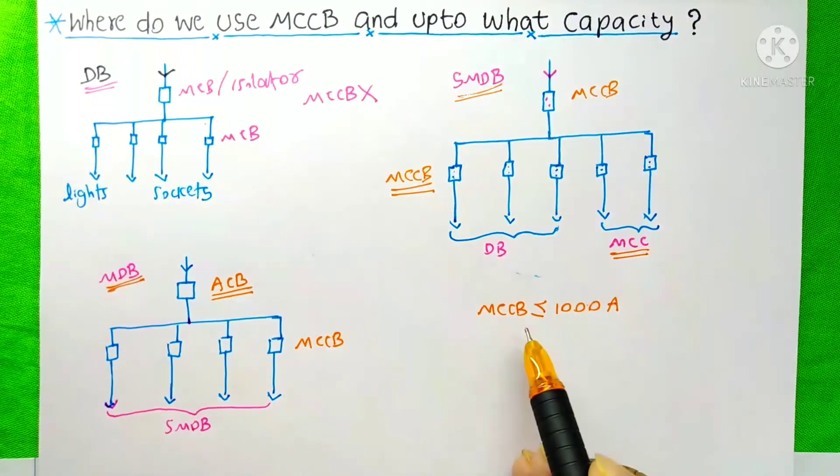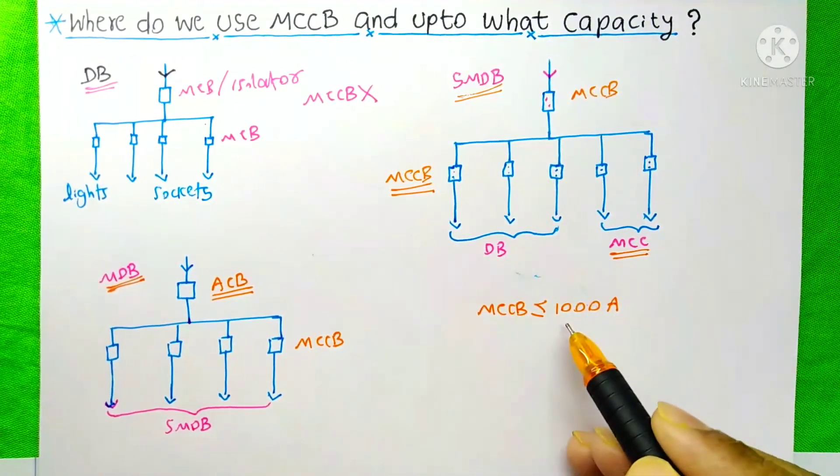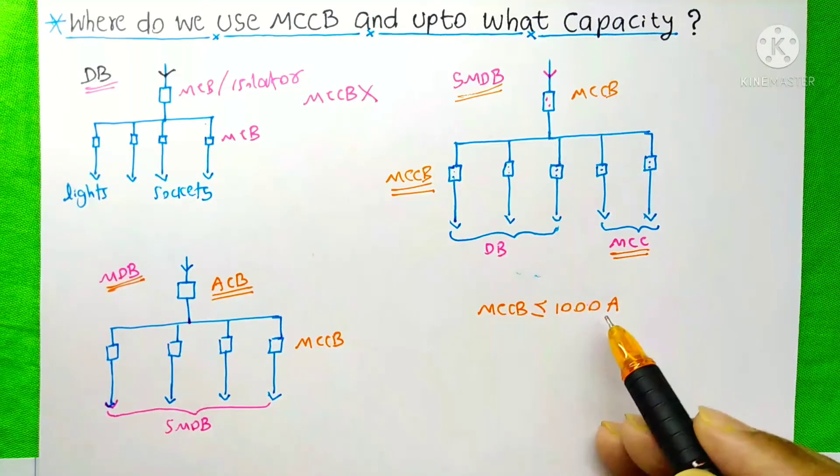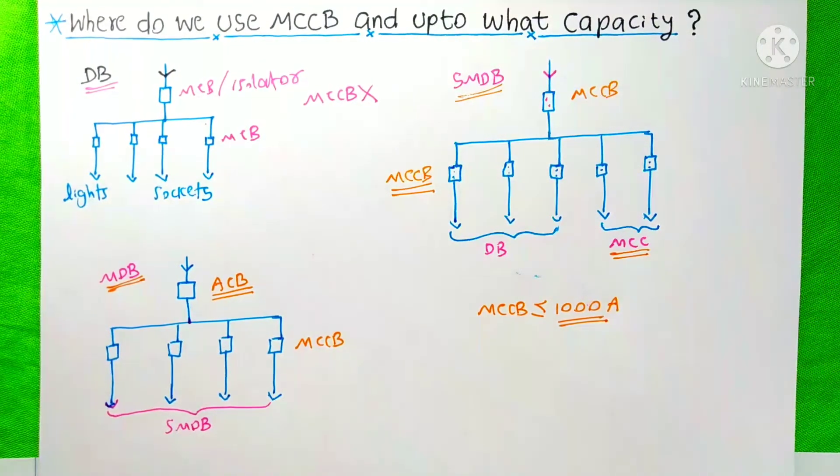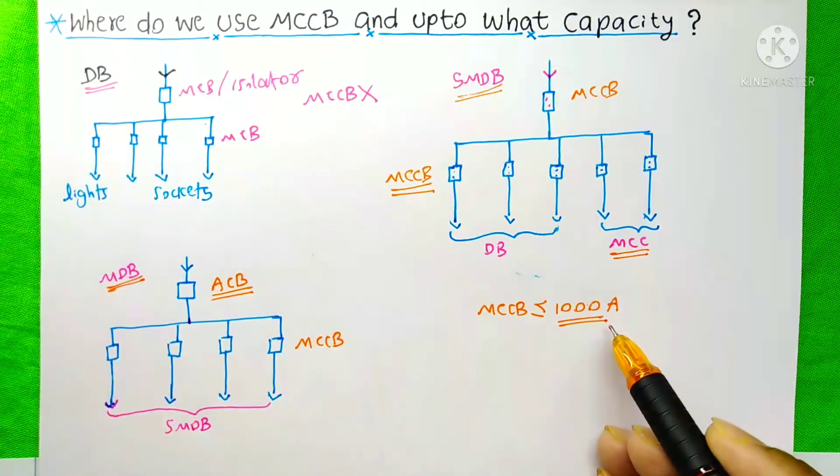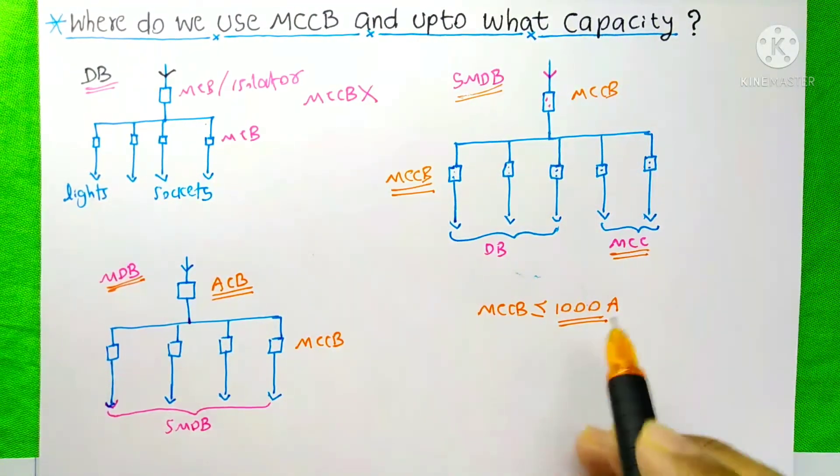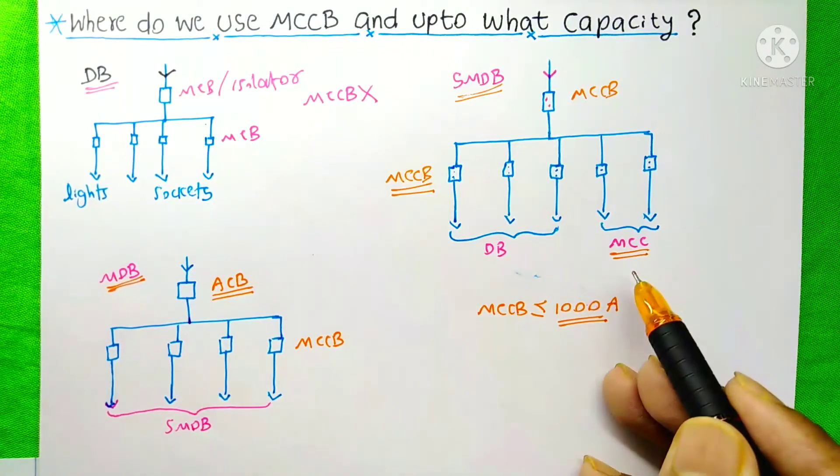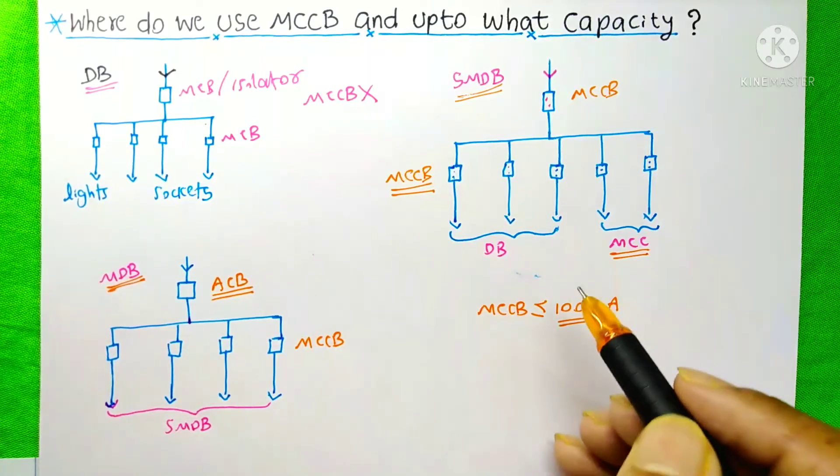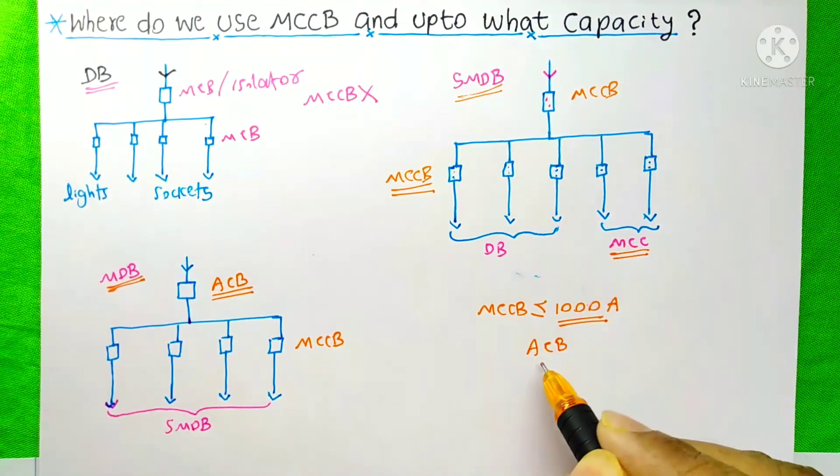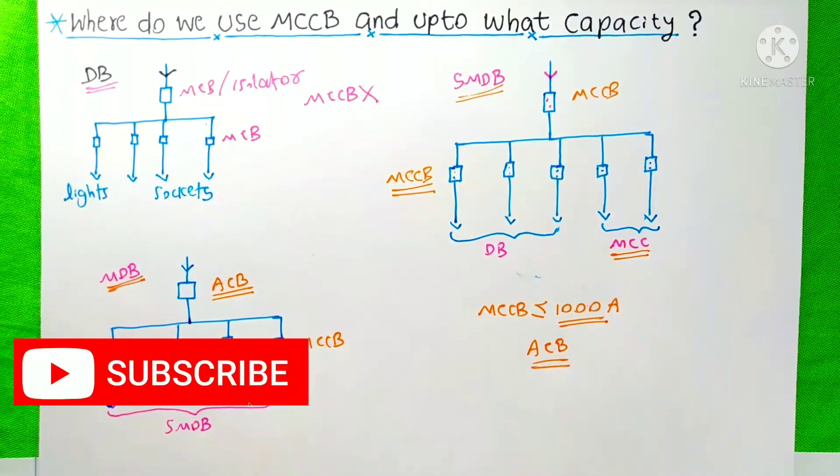Generally we use MCCB if our circuit breakers rating is less than or equal to 1000A. MCCB is available for more than 1000A also in the market. But, generally we use up to 1000A. Above this 1000A, we generally use air circuit breaker or ACB for our purpose.